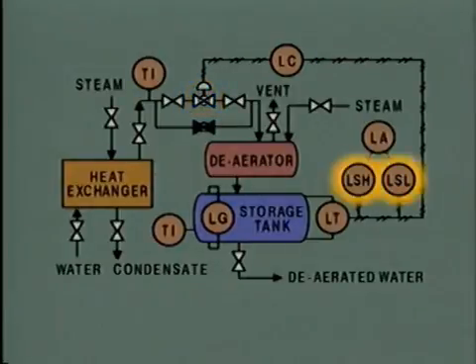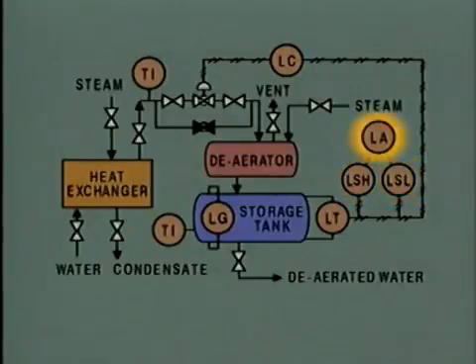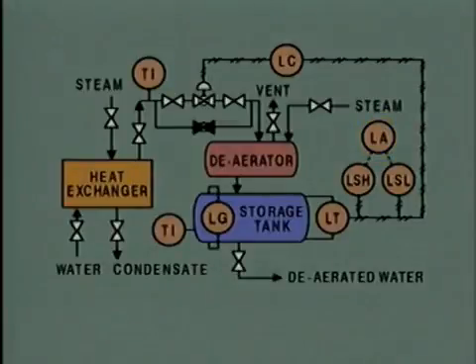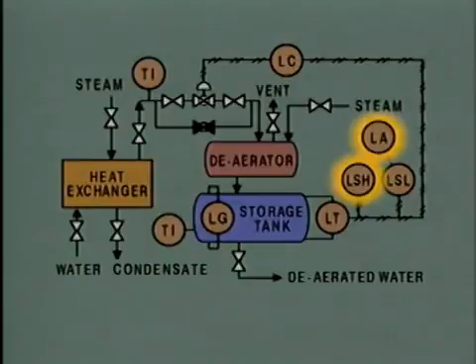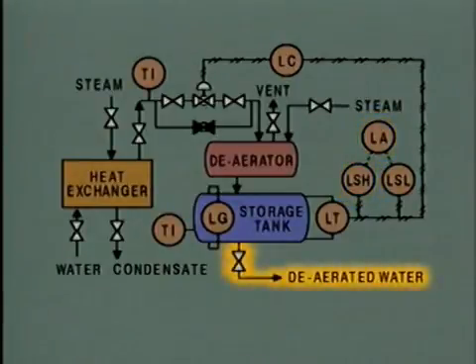These symbols represent level switches that are connected by electrical signal lines to a remote level alarm. If the level in the storage tank gets too high or too low, one of the level switches activates the alarm. The deaerated water leaves the storage tank through this line.